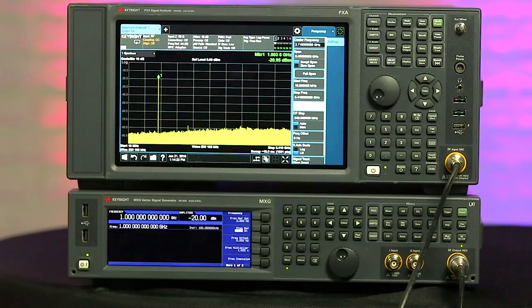In our setup here, we're using a signal generator to play the role of our DUT, and it's transmitting a signal at one gigahertz. Looking at our signal analyzer, we see our signal and a bunch of noise. There doesn't appear to be any distortion — but we know there's always some amount of distortion. I would expect to at least see the second and third order harmonics, but because the noise floor is so high, they're probably buried in there. This is where we want to improve our dynamic range, and one of the quickest and easiest methods is to narrow the resolution bandwidth of our analyzer.